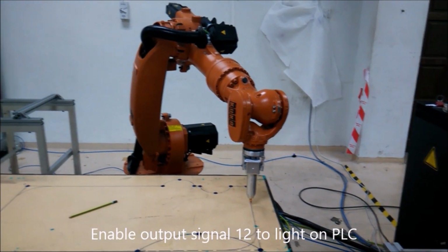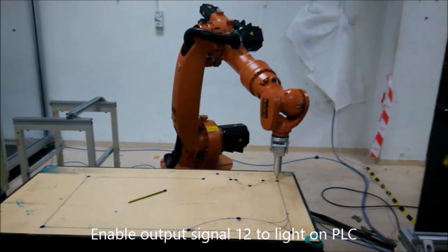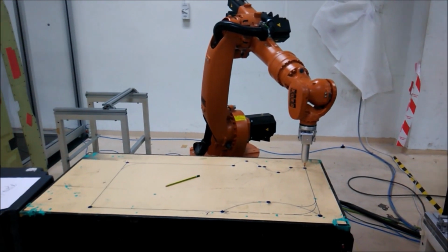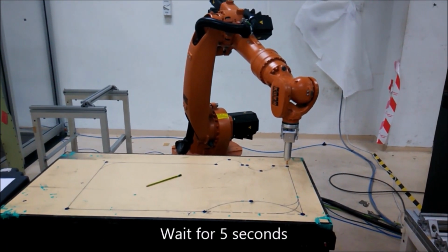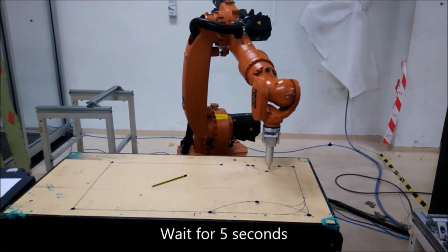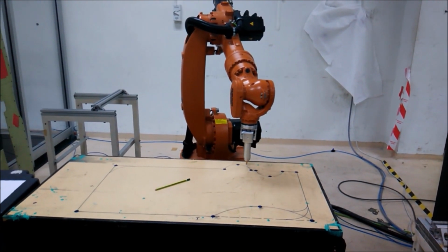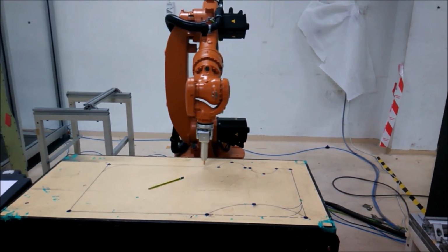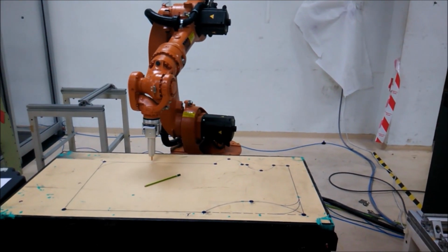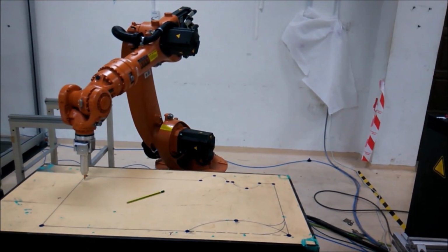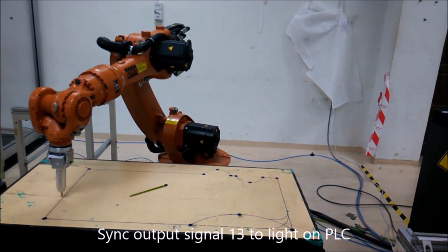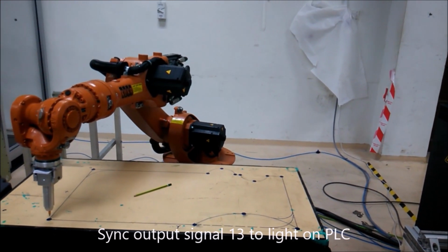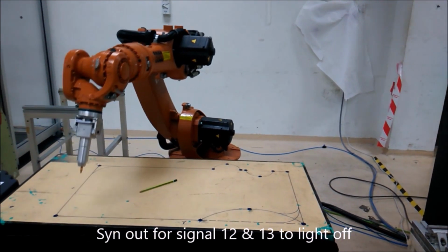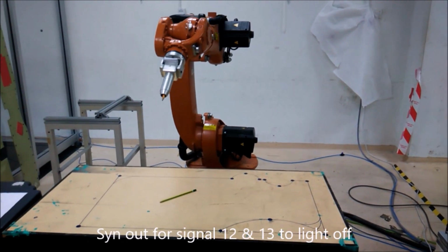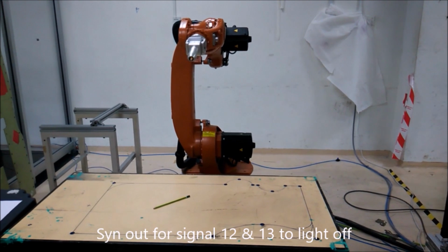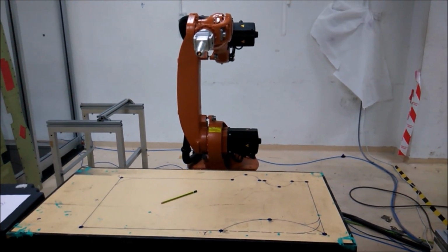So at this point, it's a P5 linear motion. The output 12 will be enabled, and at this point, it's going to delay for 5 seconds just now. So now the KUKA robot continues its movement. So basically now the output 12 and output 13 will both be switched off, and the KUKA robot will return back to its home position.